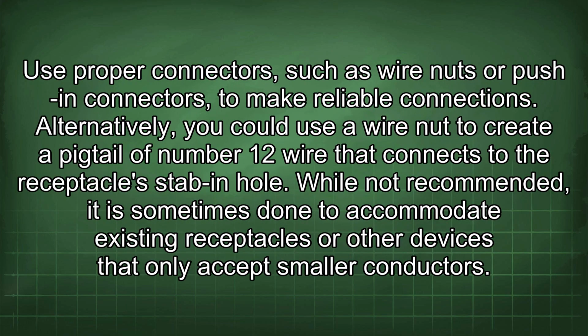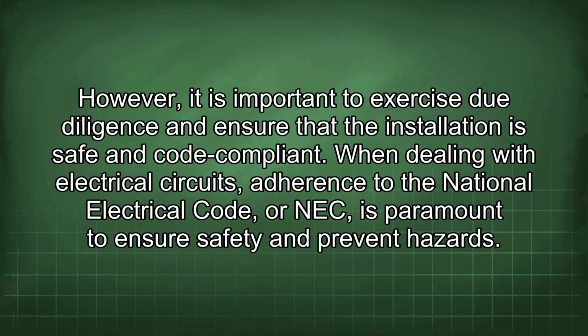Use proper connectors, such as wire nuts or push-in connectors, to make reliable connections. Alternatively, you could use a wire nut to create a pigtail of number 12 wire that connects to the receptacle stab-in hole. While not recommended, it is sometimes done to accommodate existing receptacles or other devices that only accept smaller conductors. However, it is important to exercise due diligence and ensure that the installation is safe and code compliant.